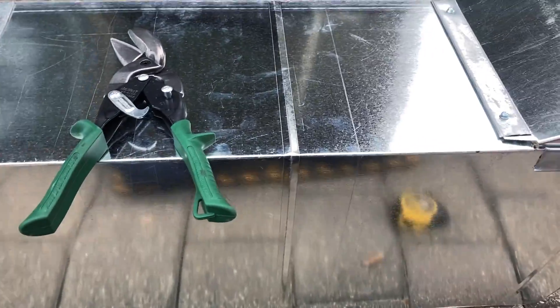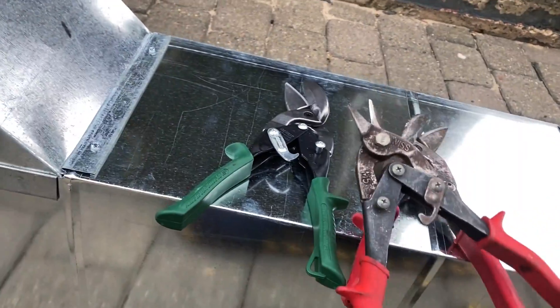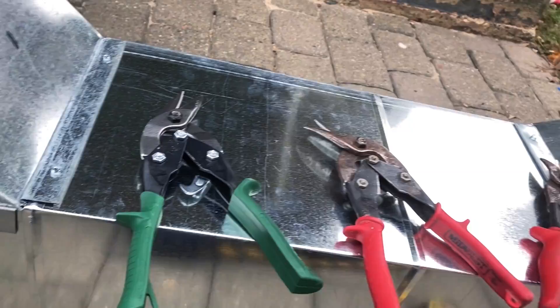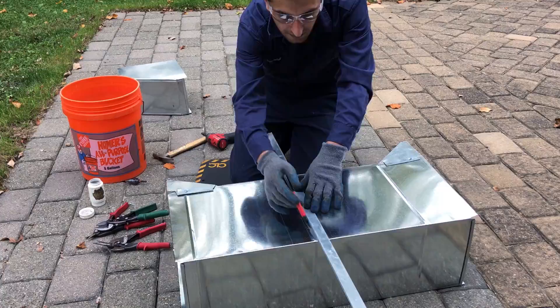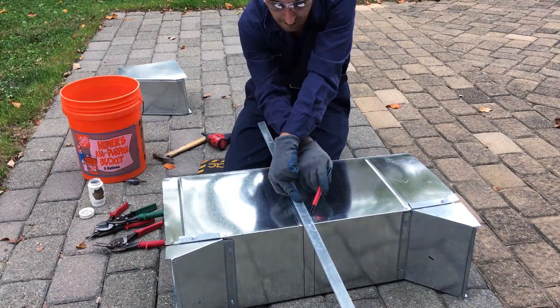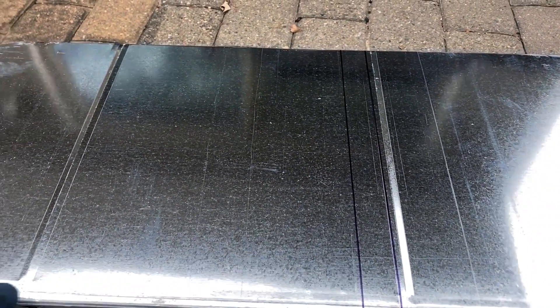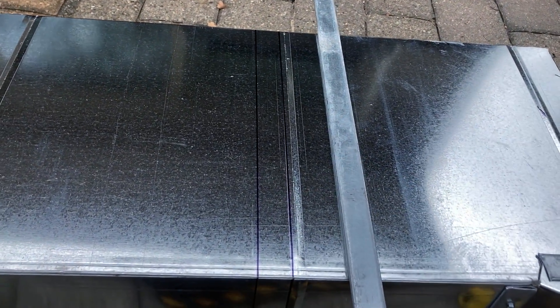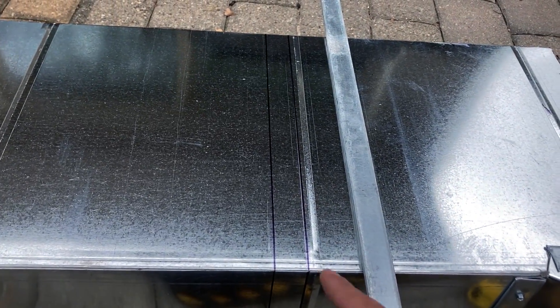This is a green handle and red handle snips — that's all you need. I have some heavy-duty snips with a short tip: this one is made by Wiss, this one is Midwest — I like them. I'm going to show you how it's done. First you mark where you need your cut. Let's say you will need this piece and also this piece. The way I do it is lay a piece of slip or drive and mark on both sides. You get about an inch and an eighth in between, which is more than you need to make your cut.